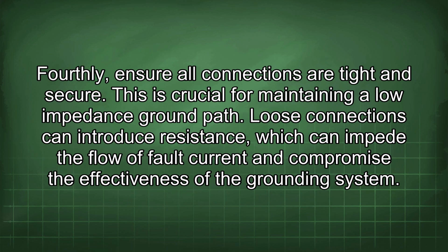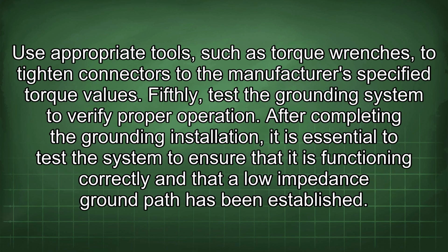Fourthly, ensure all connections are tight and secure. This is crucial for maintaining a low impedance ground path. Loose connections can introduce resistance, which can impede the flow of fault current and compromise the effectiveness of the grounding system. Use appropriate tools, such as torque wrenches, to tighten connectors to the manufacturer's specified torque values.